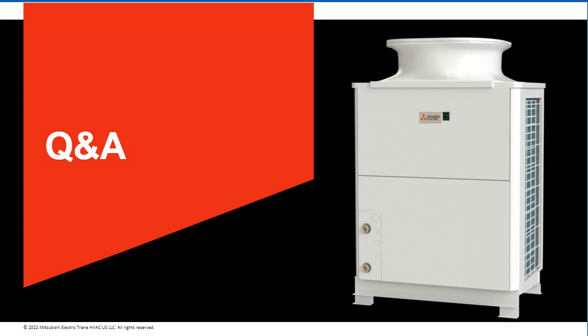All right. Can the swing tank be heated with a secondary CO2 heat pump? I'll answer that one. So we will have other provisions of other heat pumps that will be better suited for that in the future, but it would not likely be a CO2-based heat pump just because of the natural low delta T that you would want on that swing tank. Just kind of doing that maintenance load, we would likely provide more of a multi-pass style heat pump that would more than likely be a HFC-based refrigerant with a similar low GWP refrigerant.